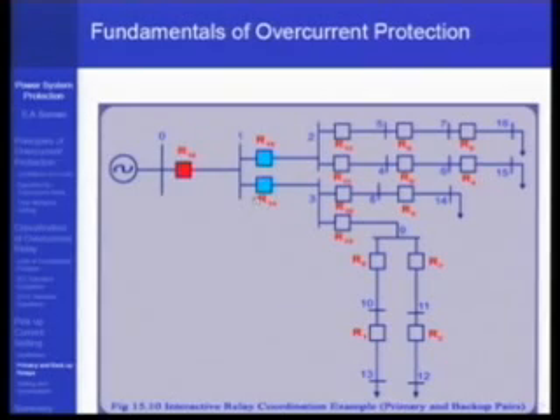So is this clear? I mean, I think it's pretty clear now. Red indicates the relays which are being set. So these 5 relays are set first. Then the relays which are backing them are set. You clearly show that these are the relays which you are backing. These are the relays which are set now. Short circuit current will be different. Yes. I will take an example of relay coordination. Right now we are just seeing the sequence.